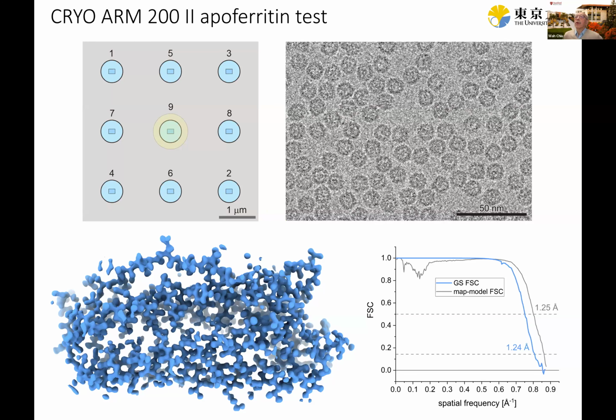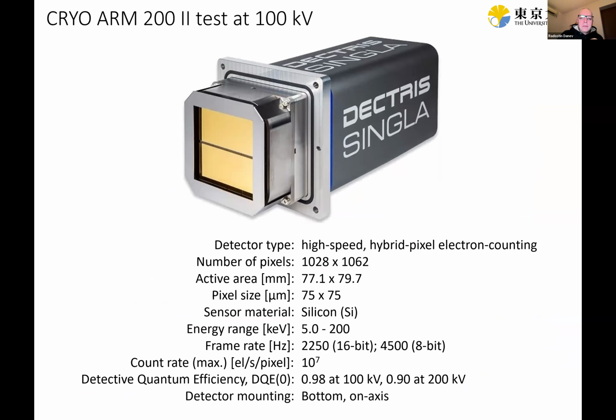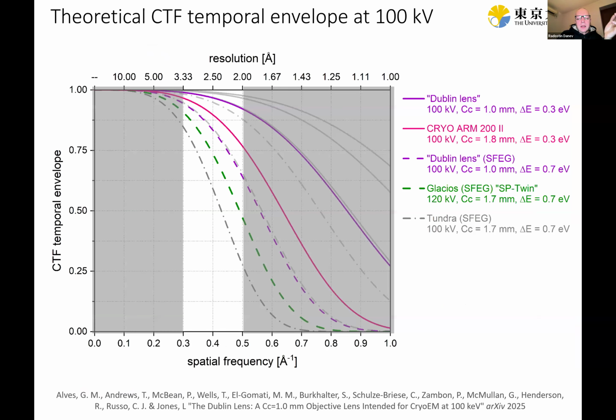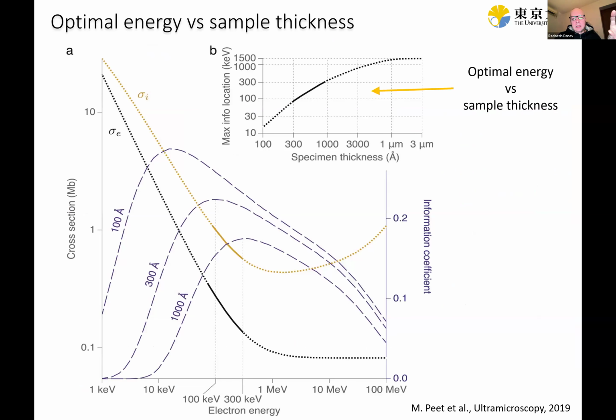Thank you. So the one question, for those who want to do tomography with 200 or 100 kilovolt, what kinds of considerations would you recommend? Well, I would say go to a 300 machine. It only makes sense to do tomography if your sample is thin. So you saw the plot here. Consider what the tilt angle range would be, and if you do plus minus 60, the sample thickness is doubled at the 60-degree tilt angle. So if you want to collect at 200, you either use a limited tilt range or, I don't know, it depends on the type of sample.